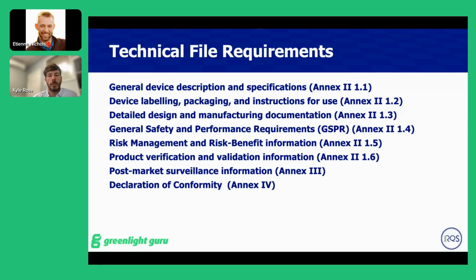The general safety and performance requirements. So this GSPR activity is a risk management activity going through the template provided from the EU MDR regulations that outlines different types of risk and whether or not they apply to your device. The risk management and risk benefit information, or benefit risk, it should also be included in your technical file. So the actual output of your risk plan, your hazard analysis and any FMEAs, and your benefit risk analysis and your risk report, this information will be in your technical file.